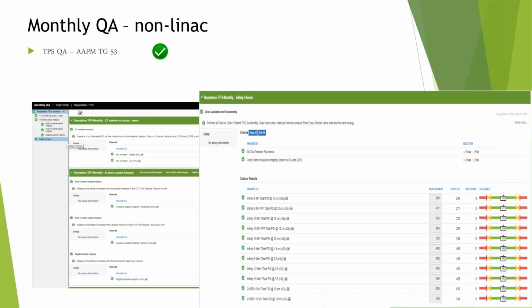The treatment planning system, we adapted the non-Linac module as well, and we're now compliant with all of AAPM Task Group 53 recommendations. We have verification of the DICOM transfer functionality, the CT number to density integrity, as well as the dose calculation consistency. We also send the CatPhan over to the treatment planning system and keep an eye on the spatial integrity.